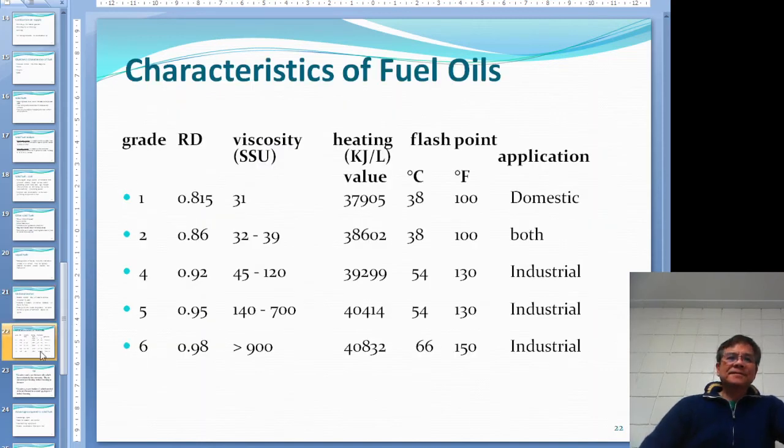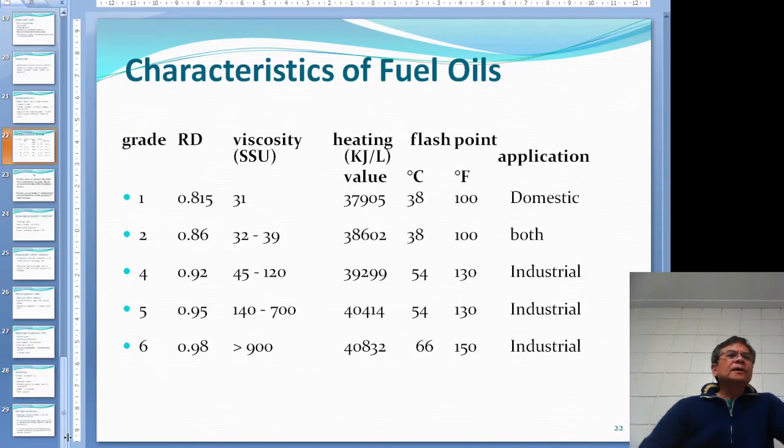Now in this table, the characteristics of fuel oil, I don't think anybody will ask you to memorize anything. But one thing you need to know is, as the grade goes up from number 1, 2, the relative density goes up. Okay, the viscosity also goes up. Now the heating value is really debatable. It depends on how much ash content is in the oil too. So this one is pretty debatable.